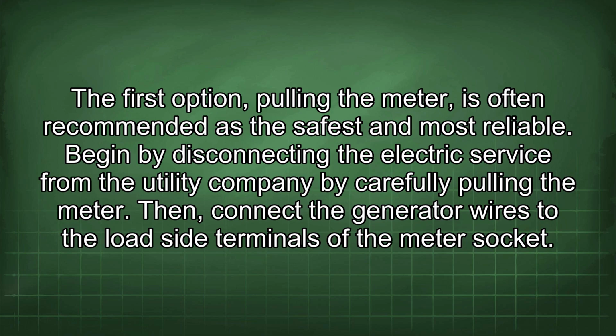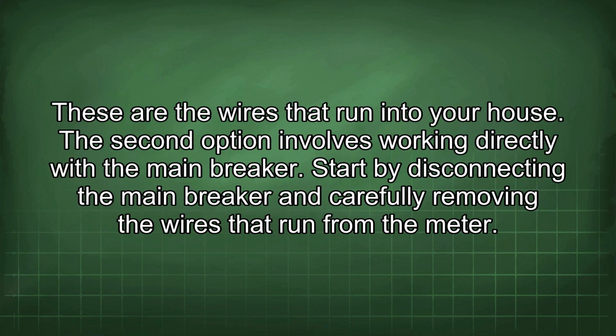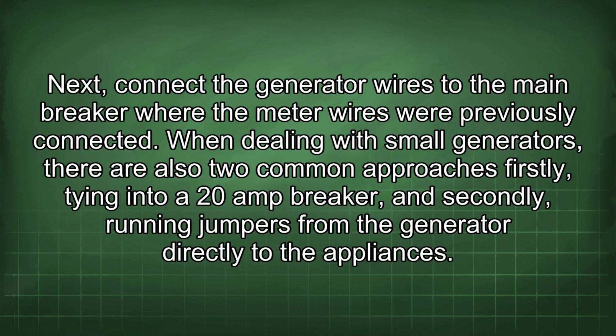Begin by disconnecting the electric service from the utility company by carefully pulling the meter. Then connect the generator wires to the load side terminals of the meter socket. These are the wires that run into your house. The second option involves working directly with the main breaker. Start by disconnecting the main breaker and carefully removing the wires that run from the meter. Next, connect the generator wires to the main breaker where the meter wires were previously connected.